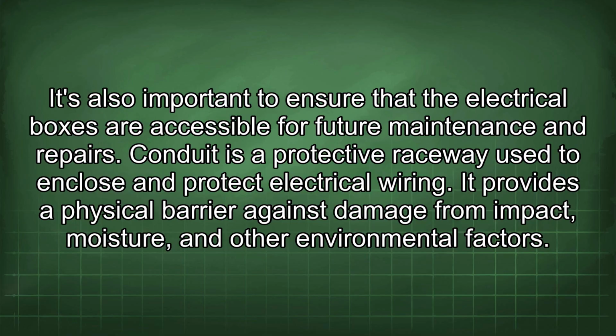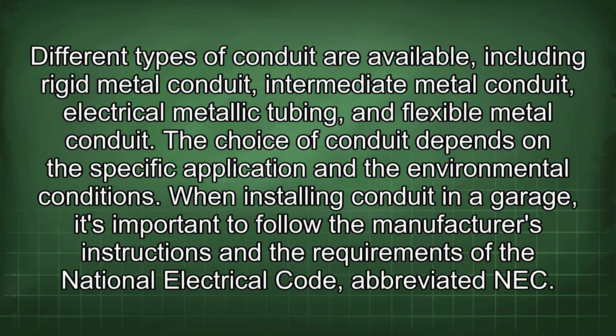Conduit is a protective raceway used to enclose and protect electrical wiring. It provides a physical barrier against damage from impact, moisture, and other environmental factors. Different types of conduit are available, including rigid metal conduit, intermediate metal conduit, electrical metallic tubing, and flexible metal conduit. The choice of conduit depends on the specific application and the environmental conditions.